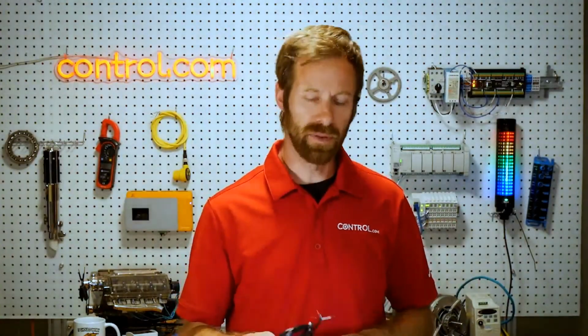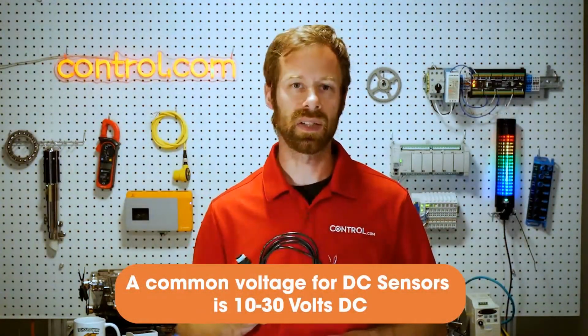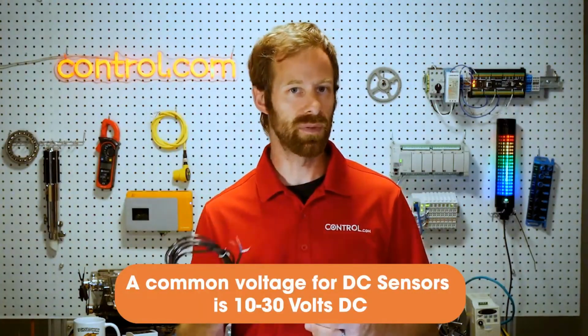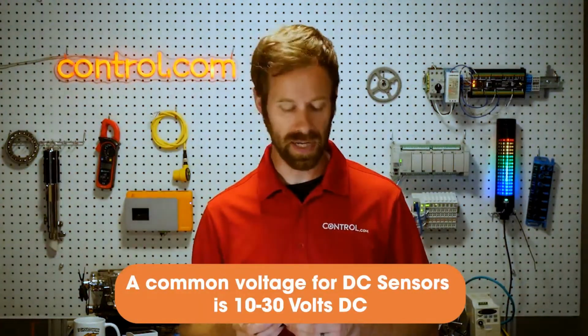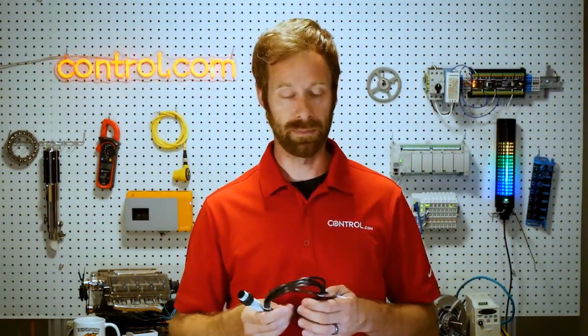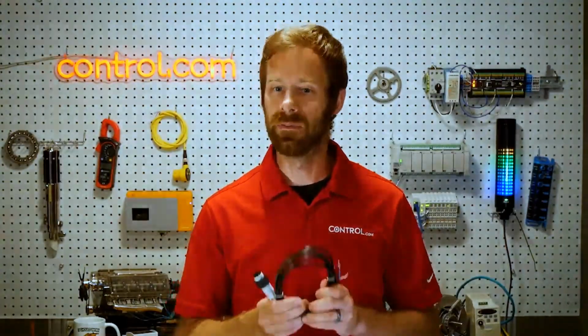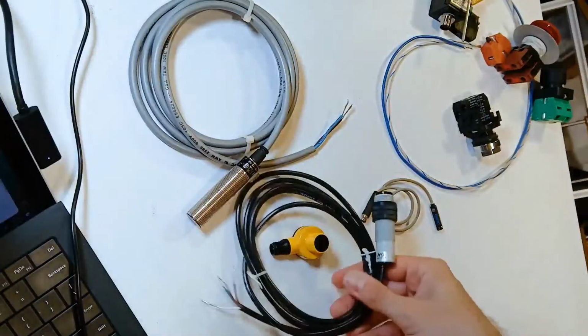So a very common voltage for DC sensors like this is 10 to 30 volts DC. So a 12-volt system, 24-volt system, those are great. Apply 5 volts, it's not going to be enough to run the sensor. Apply too much, say 120 volts AC accidentally, and you will destroy the sensor. So we have to be very careful about those parameters.